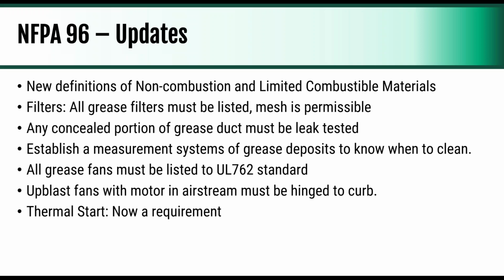Filters, there were some manufacturers selling hoods without listed filters, and there were also some service companies selling non-listed filters to be used in kitchen hoods. That is no longer permissible under NFPA 96. Another update is that any concealed portion of the grease duct must be leak tested. Many municipalities were doing this anyways, but it is now part of NFPA 96. So anyone who has adopted 2014 should be doing leak tests on concealed portions of ducts.